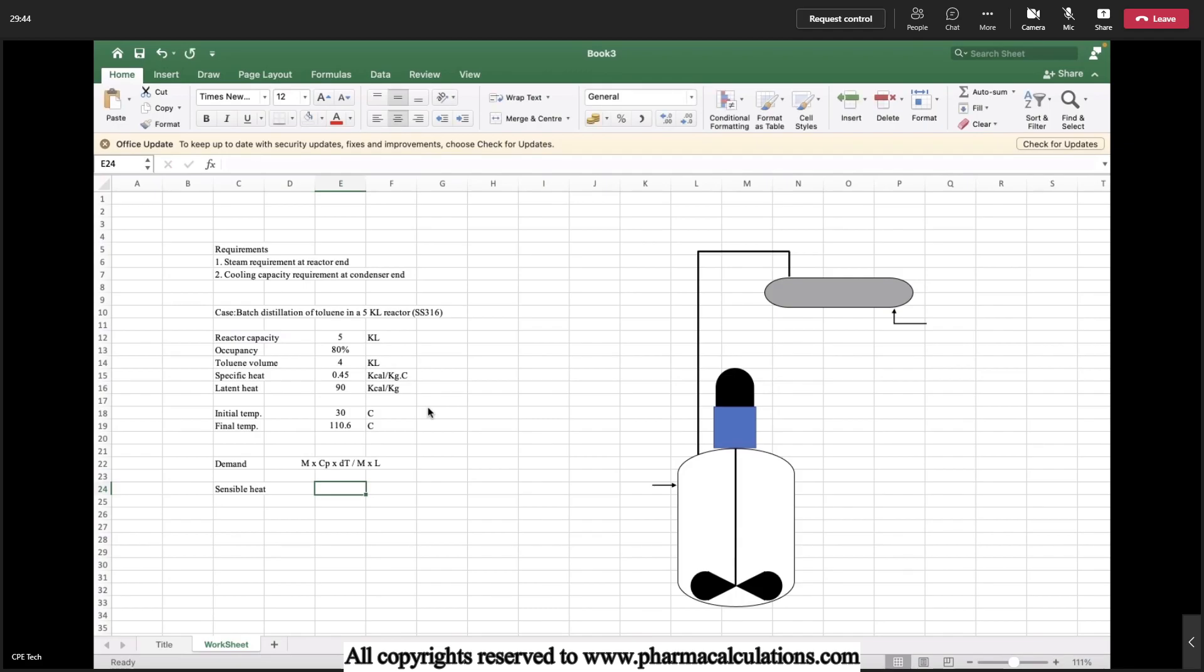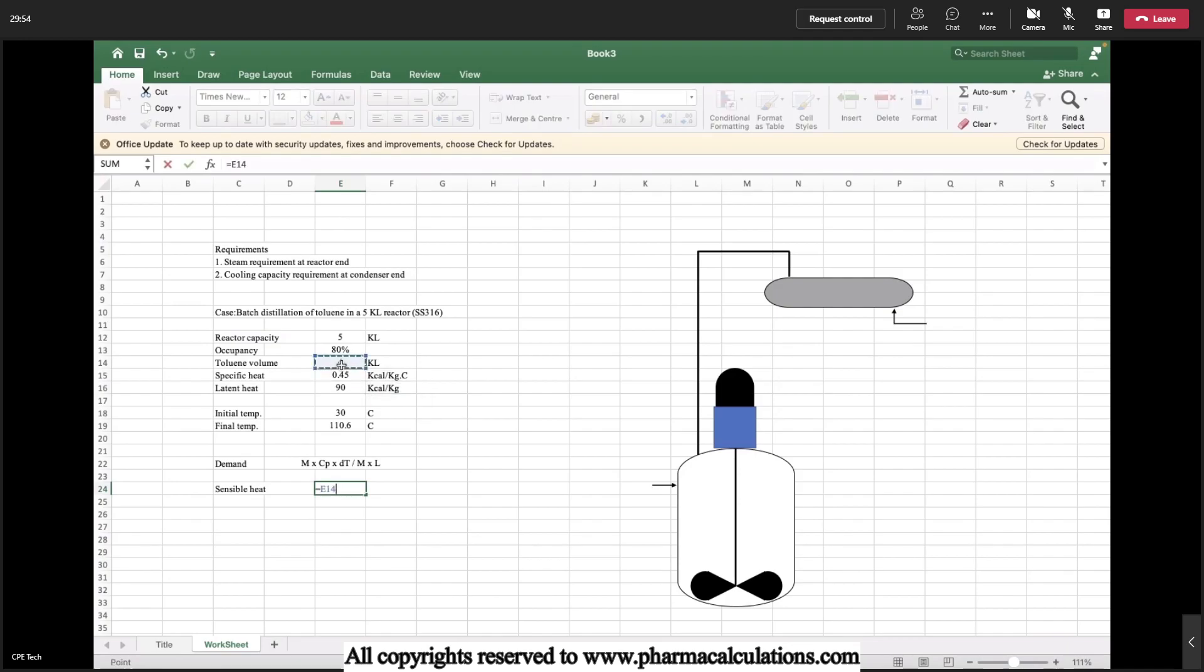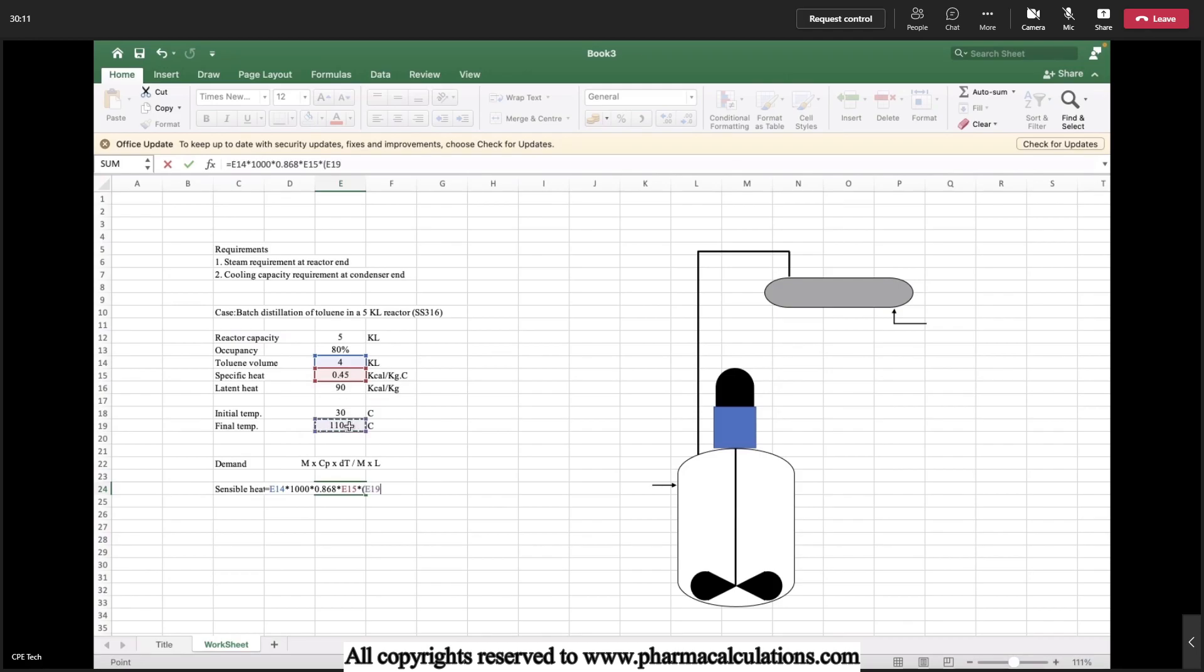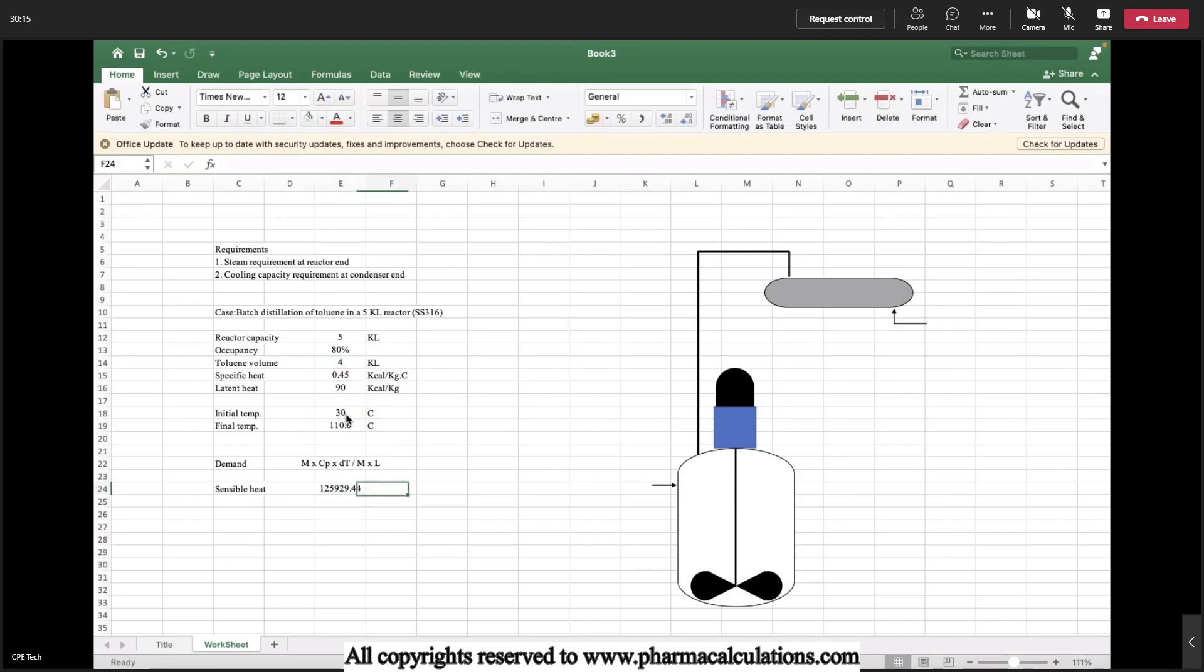The sensible heat: here M corresponds to the mass flow rate, so mass flow rate is nothing but volumetric flow rate multiplied with density. The volume is 4KL, so 4 into 1000 multiplied with density that is 0.868, multiplied with Cp, the specific heat 0.45, again multiplied with the delta T, that is 110.6 minus 30. This is the total sensible heat.